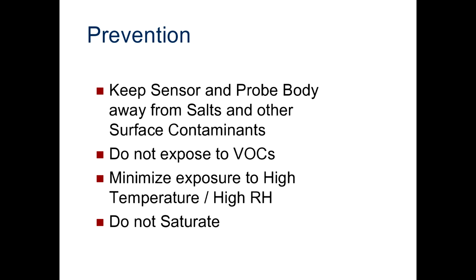Keep the sensor and probe body away from salts or other surface contaminants that may alter relative humidity. It's important to keep things as clean as possible. Do not expose the sensor or sensor body to volatile organic compounds or other solvents or cleaners. That can cause permanent damage. And minimize exposure to high temperature and RH. That can cause both hysteresis and other drift.